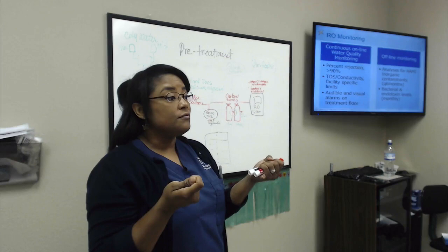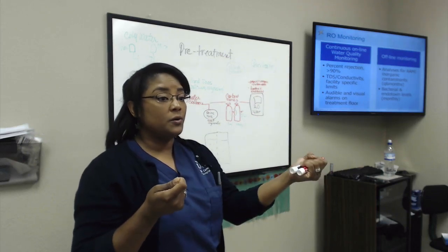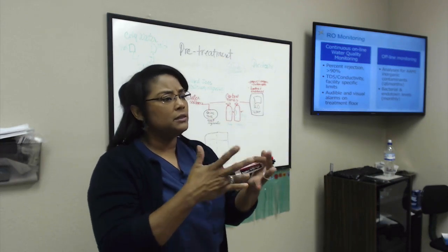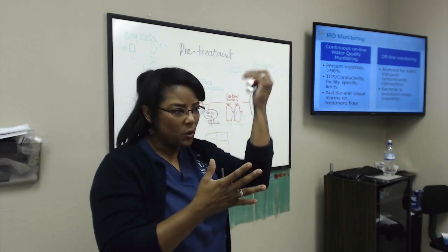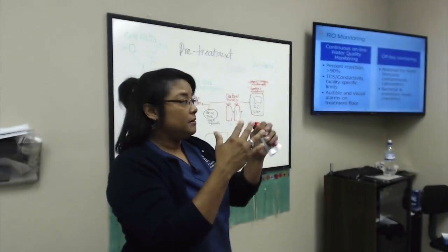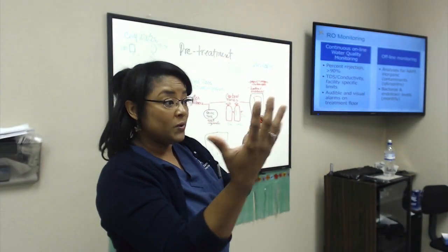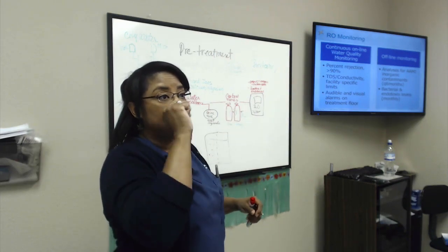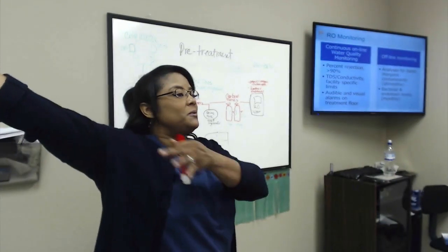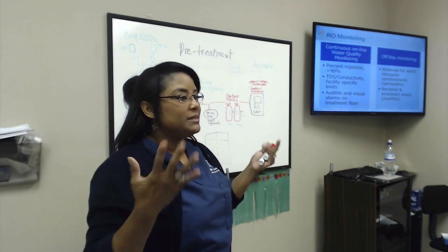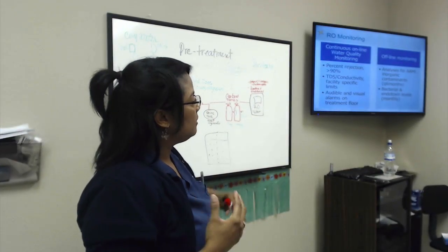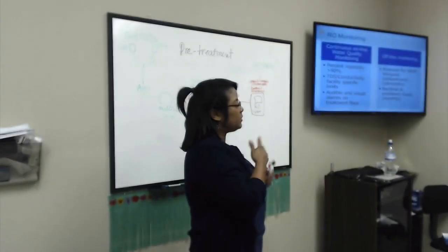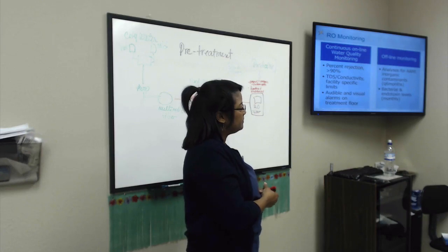What they're looking for is, the city water, we were talking about this earlier, is going to have a lot of contaminants. Aluminum, calcium, fluoride, all that, right? And then when it passes through the RO and is tested again, almost all of that has to be 0, or 0.000000, almost nothing, okay? That's what we're looking for, to let us know that the RO is working. We test for AAMI, or the contaminants, every 6 months.